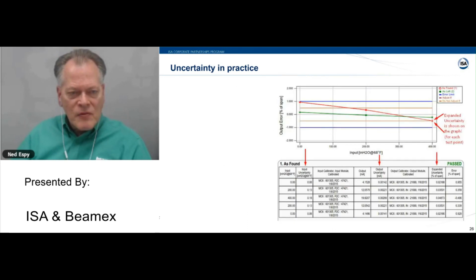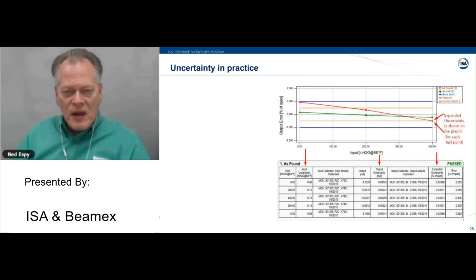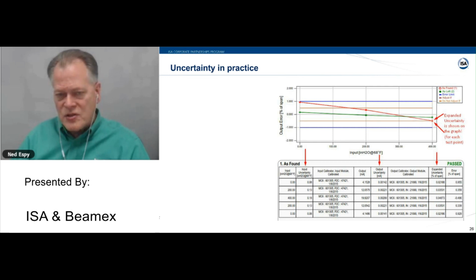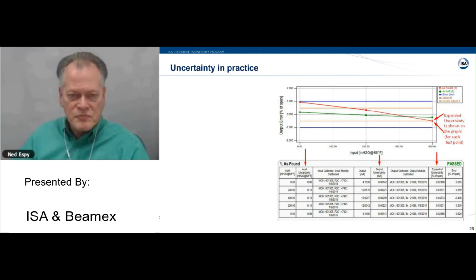And if we go back to the data, we've picked up these three columns, and it's maybe a little hard to see, but Roy showed it in his. He had a huge uncertainty for the 300 PSI module he used to make that low inches of water measurement. In this example, the expanded uncertainty is very small. It's 0.5% as compared to the 1% tolerance.